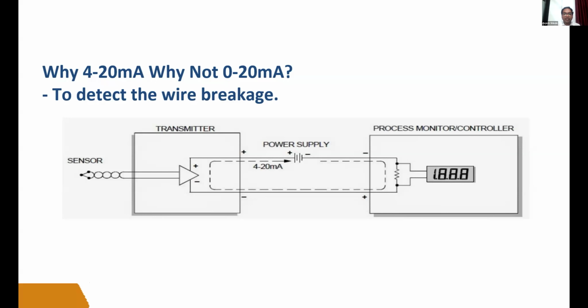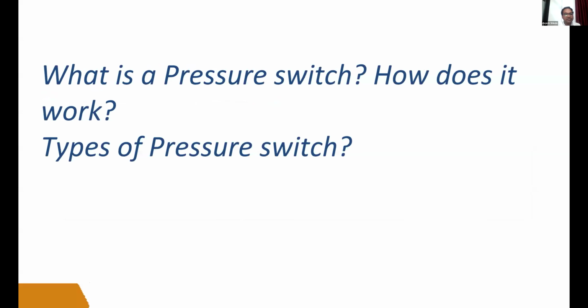In this situation, if the wire is broken, it will always show a 0 milliamp signal only. So you will not get the idea whether the pressure is 0 bar or the wire is broken. But in the second case, if you use the 4 to 20 milliamp sensor, then for 0 bar pressure it will give us 4 milliamps, and for 100 bar it will give 20 milliamps. And if the wire is broken, it will show 0 milliamps current. So that is the advantage of using the 4 to 20 milliamp sensor.